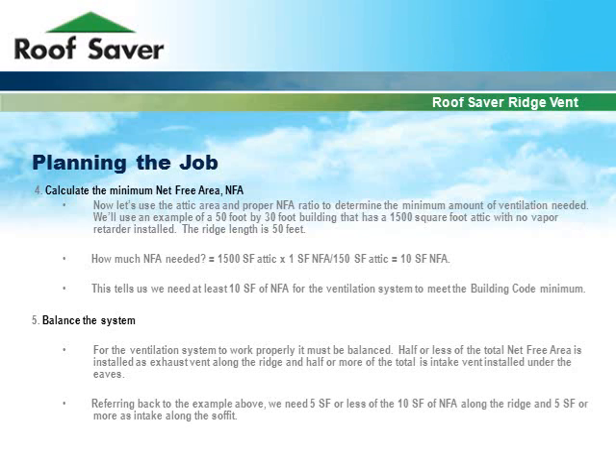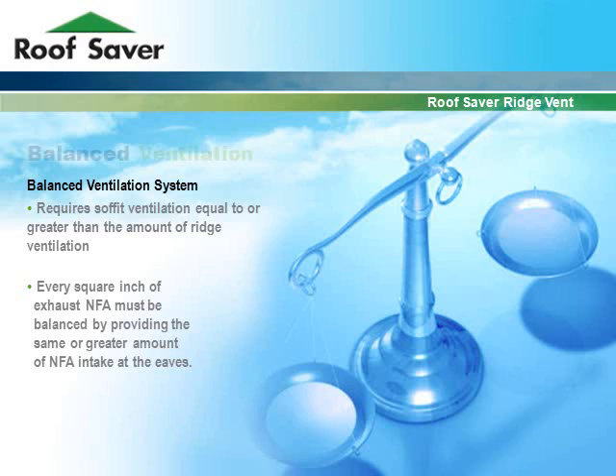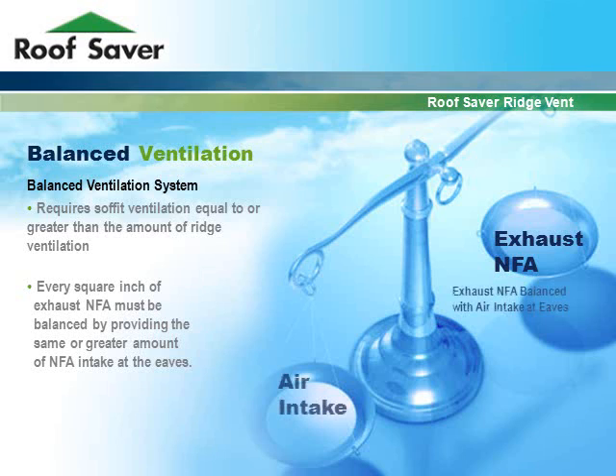For the ventilation system to work properly, it must be balanced. Half or less of the total net free area is installed as exhaust vent along the ridge, and half or more of the total is intake vent installed under the eaves. Referring back to the example, we need 5 square feet or less of the 10 square feet of NFA along the ridge and 5 square feet or more as intake along the soffit. A balanced ventilation system requires soffit ventilation equal to or greater than the amount of ridge ventilation — every square inch of exhaust net free area must be balanced by the same or greater amount of intake at the eaves.